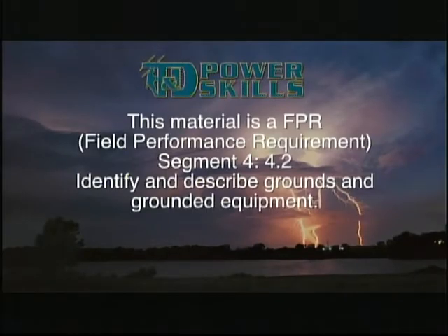Make sure you've identified which circuit is which before you climb a pole to work on them. Let's move on to another potential electrical hazard you should identify before climbing: ground wires and grounded equipment. When working on overhead lines, you must remain isolated from all grounds and grounded equipment — either by keeping a sufficient distance from them or by covering them. If you don't stay isolated and happen to come in contact with a ground wire while working on an energized circuit, you could become the path to ground.